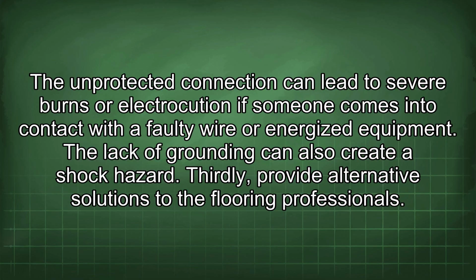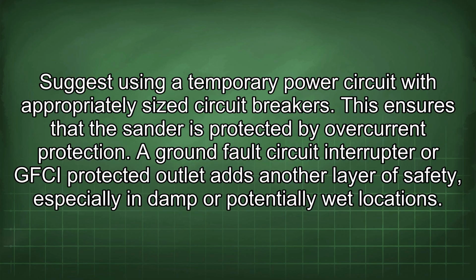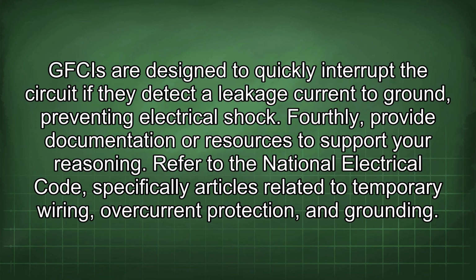Thirdly, provide alternative solutions to the flooring professionals. Suggest using a temporary power circuit with appropriately sized circuit breakers. This ensures that the sander is protected by overcurrent protection. A ground fault circuit interrupter, or GFCI, protected outlet adds another layer of safety, especially in damp or potentially wet locations. GFCIs are designed to quickly interrupt the circuit if they detect a leakage current to ground, preventing electrical shock.